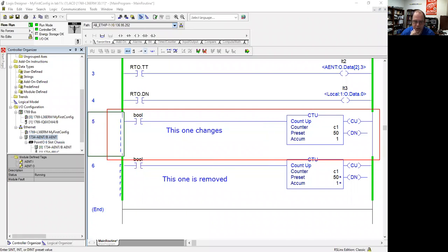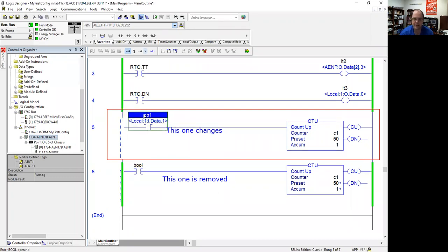in the I rung, not the R rung. If I try to make changes in the R rung, it won't work. So if I want to change this to PB1, everything operates like normal. So local, PB1. I can just have PB1. All right. And so now this is a 1-step, 2-step process. If you notice up here, another box showed up. This is my online edit setup.